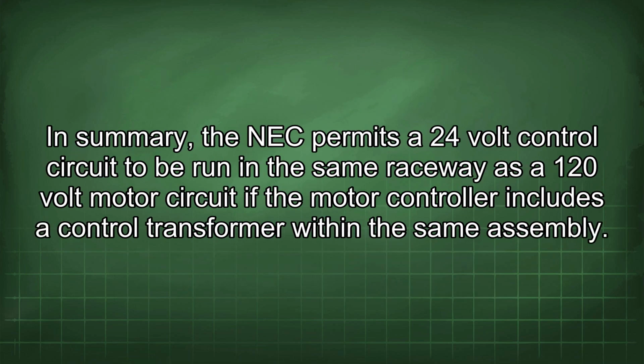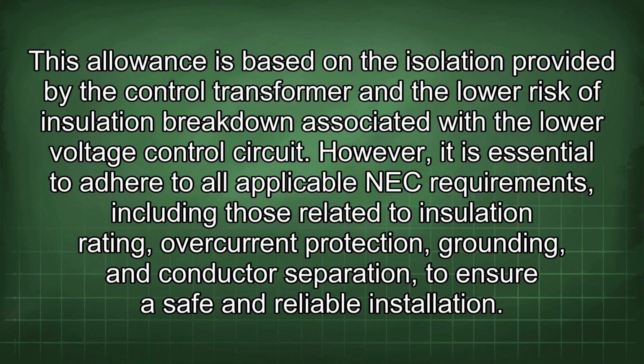In summary, the NEC permits a 24-volt control circuit to be run in the same raceway as a 120-volt motor circuit if the motor controller includes a control transformer within the same assembly. This allowance is based on the isolation provided by the control transformer and the lower risk of insulation breakdown associated with the lower voltage control circuit. However, it is essential to adhere to all applicable NEC requirements, including those related to insulation rating, overcurrent protection, grounding, and conductor separation to ensure a safe and reliable installation.